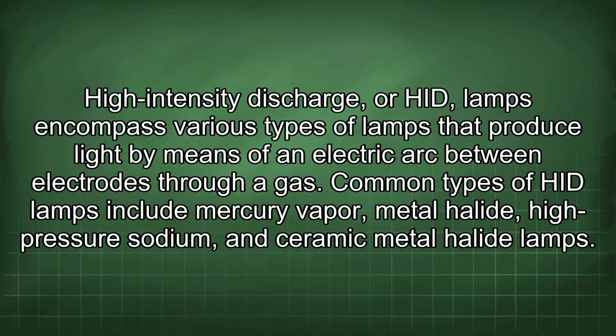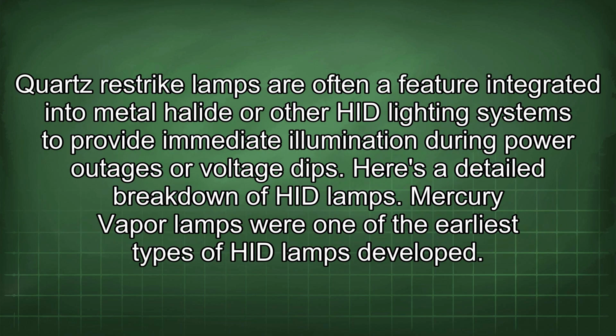Common types of HID lamps include mercury vapor, metal halide, high-pressure sodium, and ceramic metal halide lamps. Quartz restrike lamps are often a feature integrated into metal halide or other HID lighting systems to provide immediate illumination during power outages or voltage dips. Here is a detailed breakdown of HID lamps.